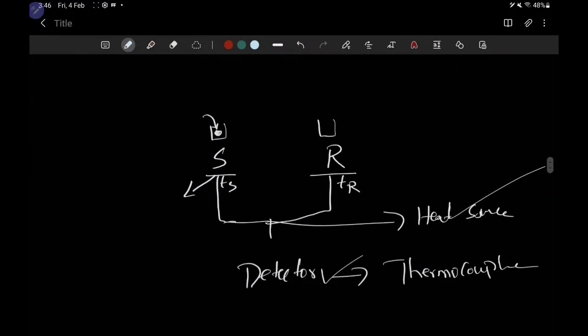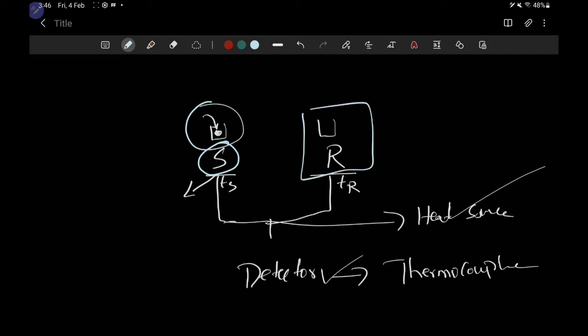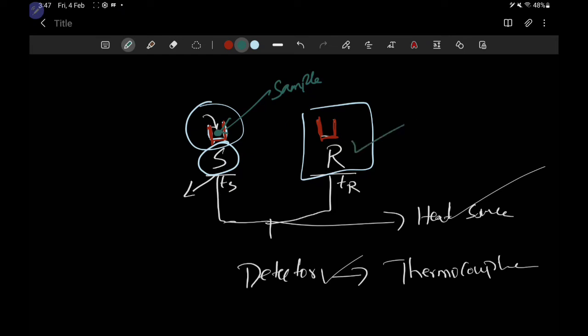Now we will study the instrumentation of DTA and DSC — both are similar. We have a sample holder where we keep the sample, and a reference holder. Sometimes the reference holder is kept empty, or we use an inert substance like silica. We use aluminum pans — one pan holds the sample and another holds the reference. There is also a heat source which supplies heat to both the sample and reference pans.